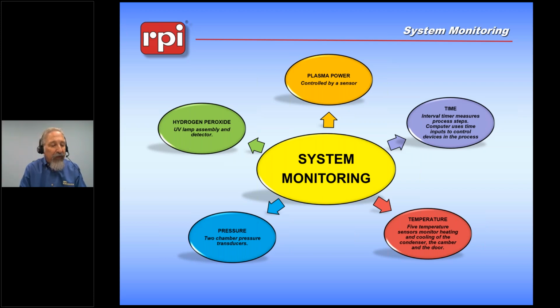There are 5 temperature sensors that look at the internal temperature in various parts of the machine, since we have to very carefully control the temperature to make sure that we keep the hydrogen peroxide as a vapor and don't recondense it again. There are 2 sets of pressure transducers, one that looks at the vaporizer condenser assembly and one that looks at the chamber directly. And of course, there's a hydrogen peroxide monitor, so we can be sure that we've delivered the hydrogen peroxide to the chamber in the correct concentration, and that concentration is monitored throughout the cycle.